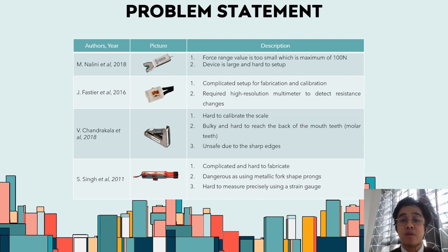The common problem is that it is hard to calibrate and not user-friendly. For the first picture, we can see that the force range value is too small, which is a maximum of 100 Newton, and the device is too large and hard to set up. For the second picture, it is a complicated setup for fabrication and calibration. It also requires a high resolution multimeter to detect resistance changes in the Wheatstone bridge circuits.